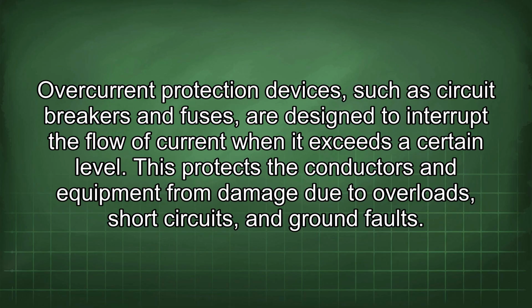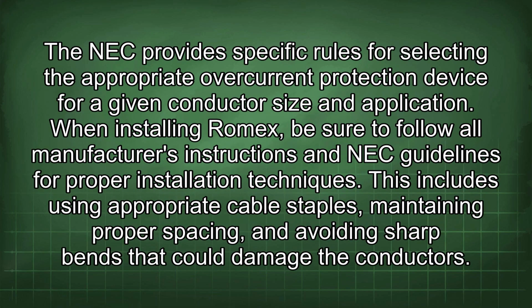Overcurrent protection devices such as circuit breakers and fuses are designed to interrupt the flow of current when it exceeds a certain level. This protects the conductors and equipment from damage due to overloads, short circuits, and ground faults. The NEC provides specific rules for selecting the appropriate overcurrent protection device for a given conductor size and application.